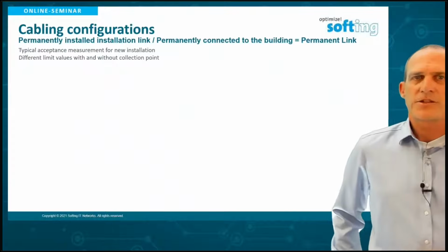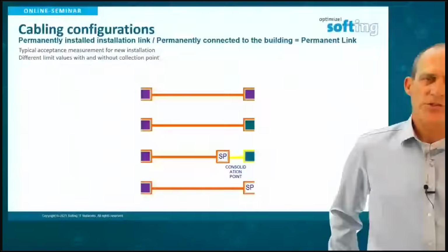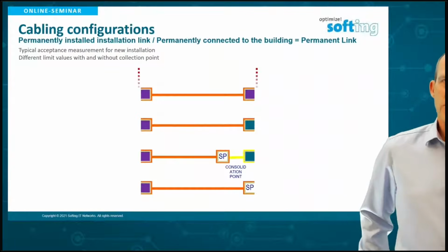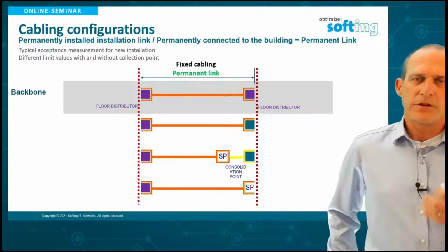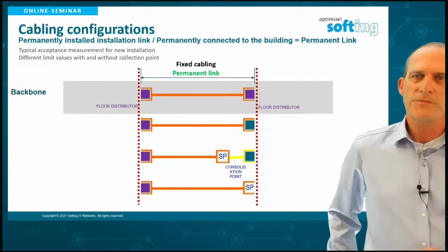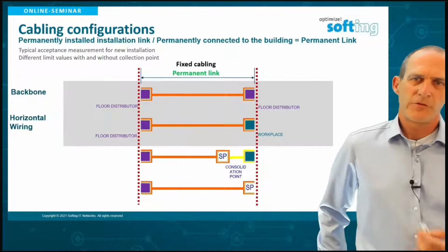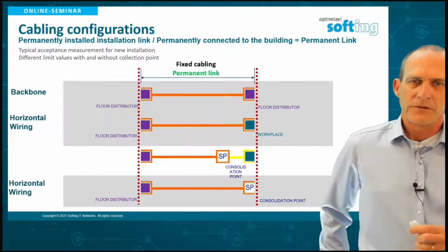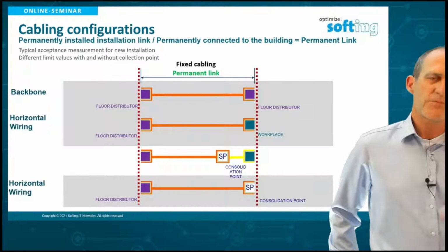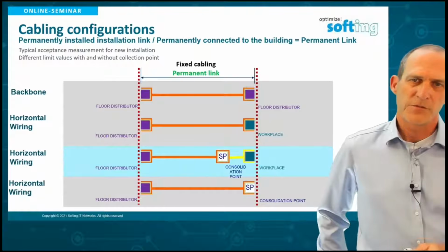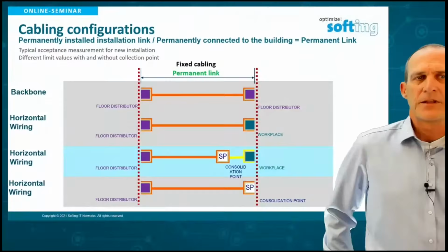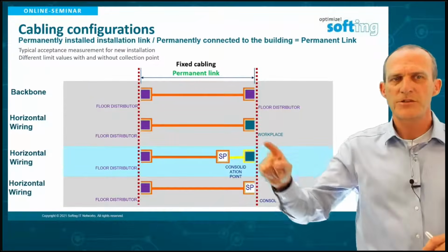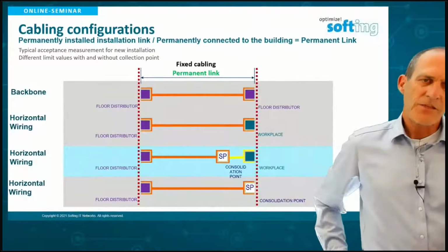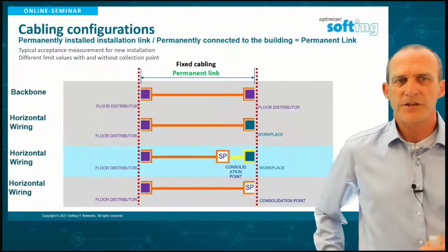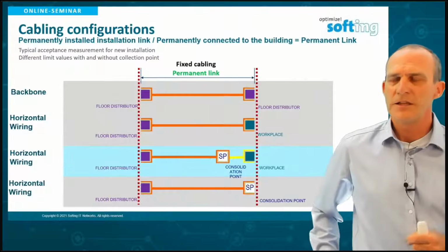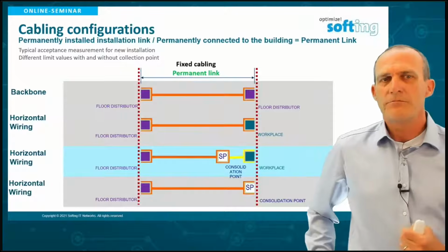Let's look at the cabling configurations. The permanent link is the link that everybody installs. It can be the fixed cable on a backbone, for example from one floor distributor to the next, from the horizontal wiring from the floor distributor to the workplace, or from the floor distributor to a consolidation point, including from the floor distributor via the consolidation point up to the workplace. The dotted lines you see in the picture are the reference planes for testing - meaning the first and last connector of the link have to be included in testing. That's always a challenge for the tester, to accurately measure the first and last connector.